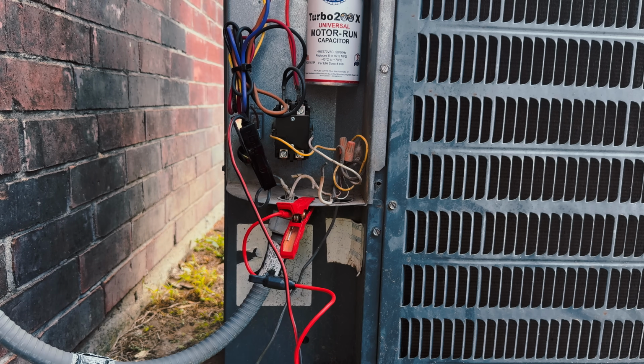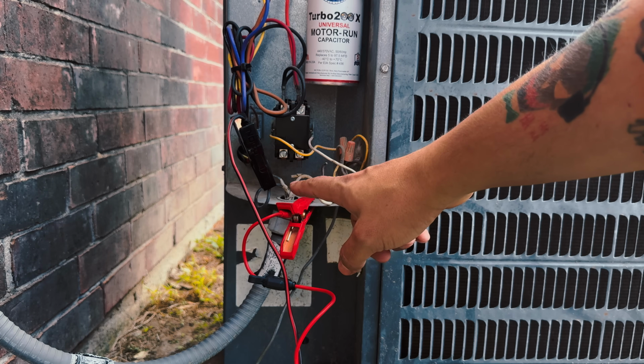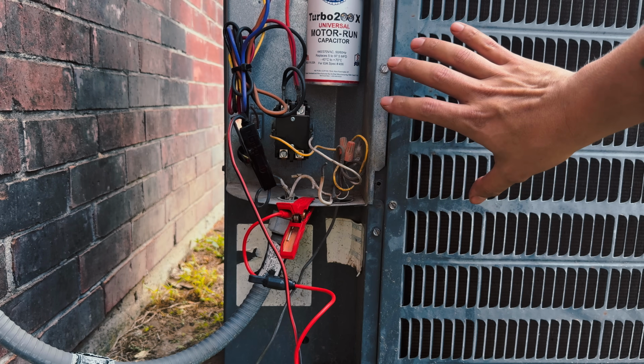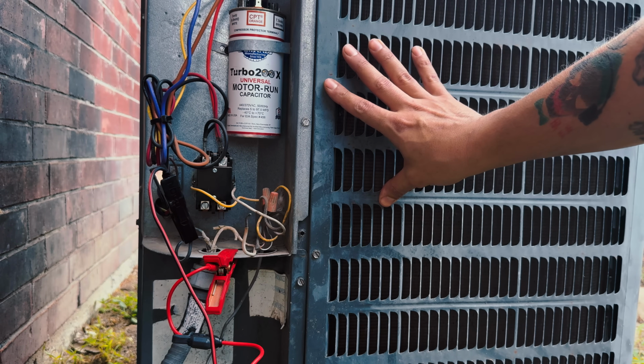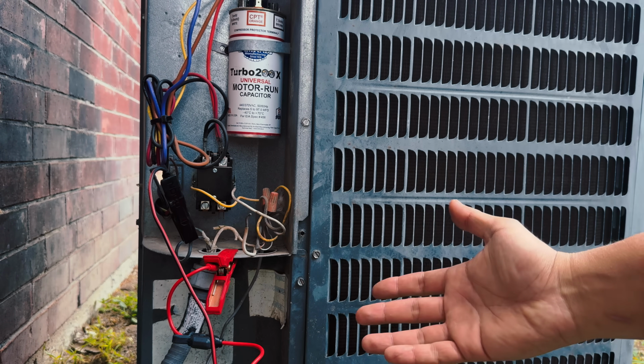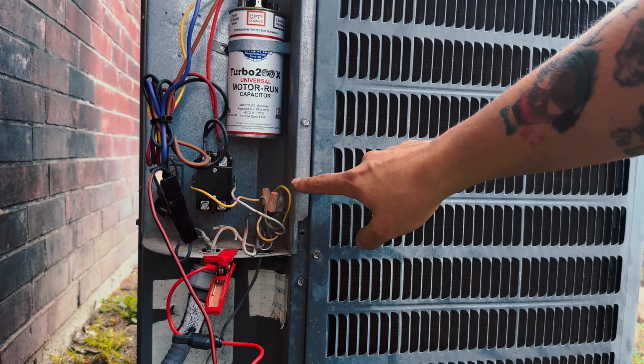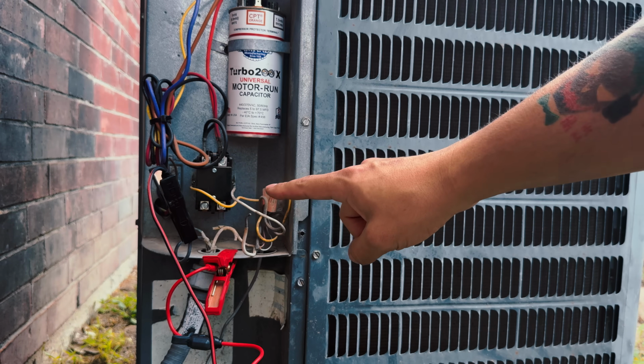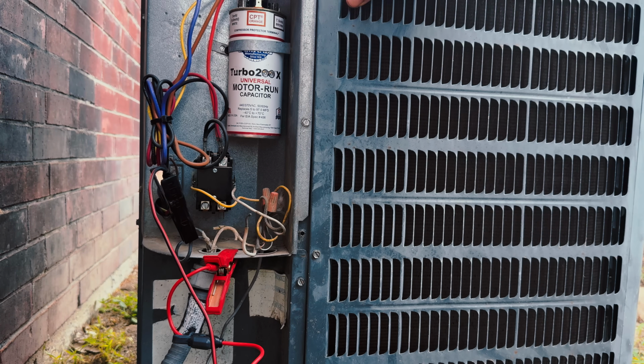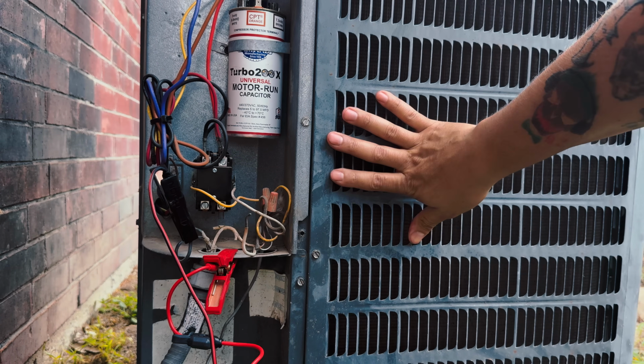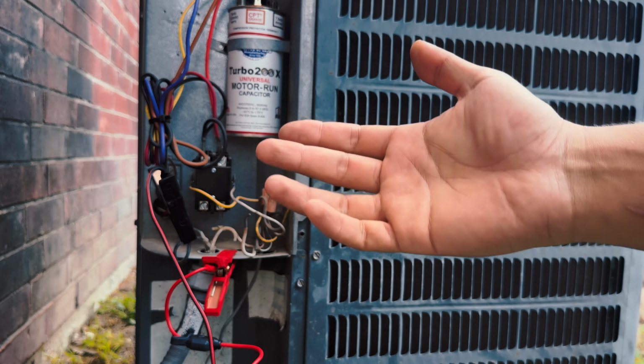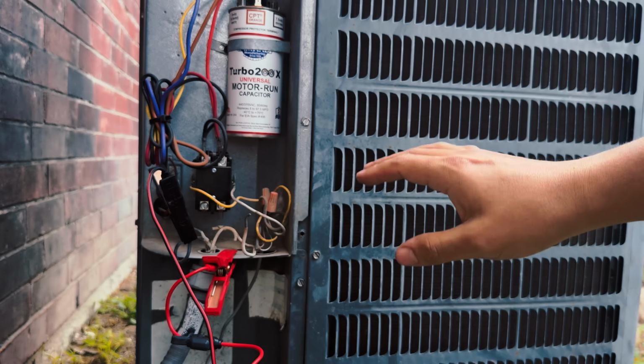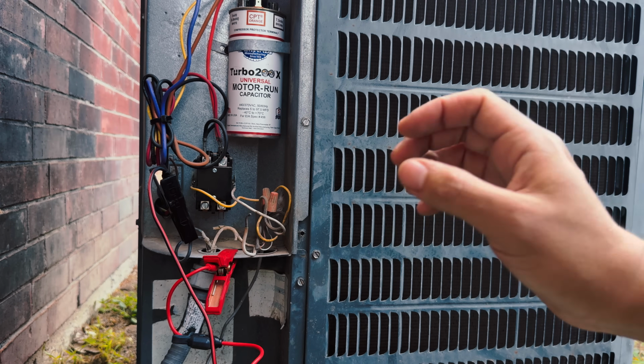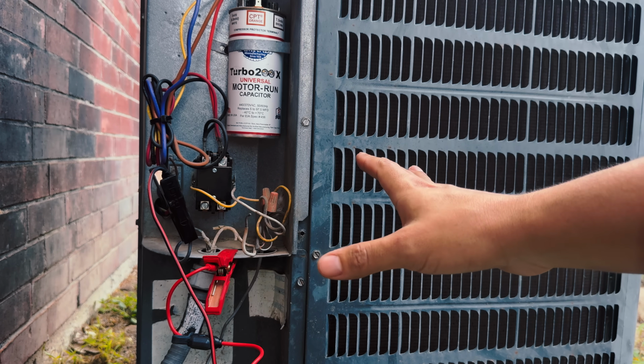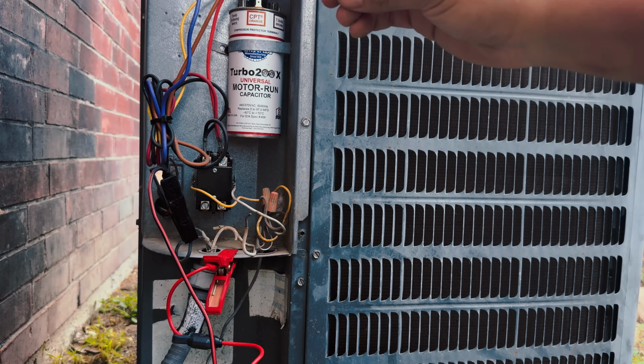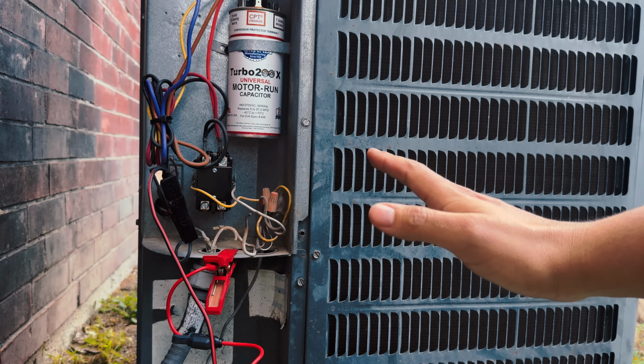So the first concern and the most common comment I get is that you are connecting to the metal of the unit - we're grounding out on the case of the unit, so it's metal that gives you the ground. And the common comment is that now I'm completing the circuit here and energizing this, and it's going to cause a bunch of shocks. If you touch this, you're going to electrify any metal from here all the way inside the house, things like that. I can't explain it, but that's the most common thing I get from electricians and experts who claim that they are. No shade to you guys.